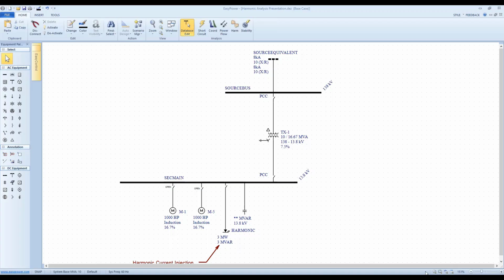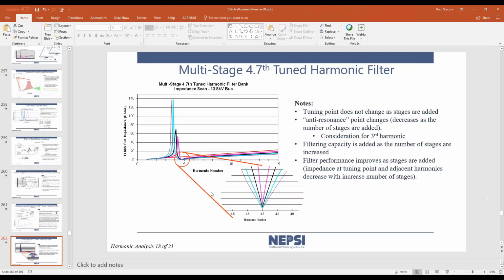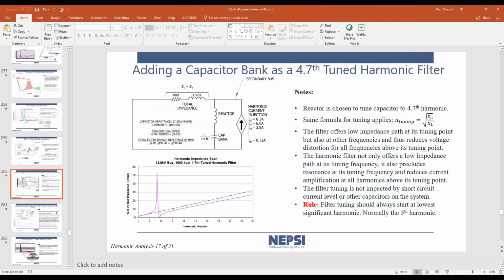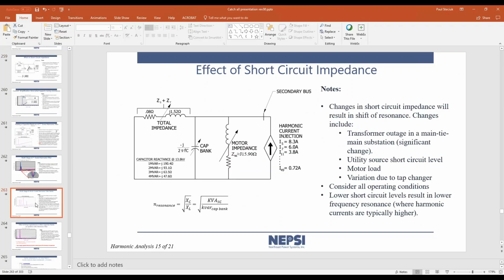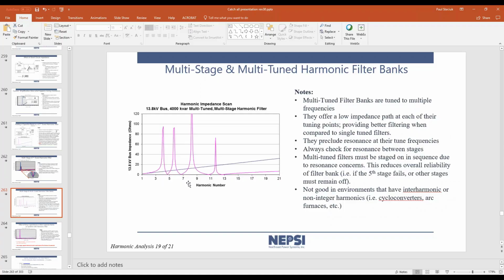And then the final question is, do you cover resonance or conditions that can be caused by filters? So first of all, harmonic filters. We go back to this, and what the question is saying is, hey, do you take care of this problem here, these resonance concerns, and here's a 5th, 7th, 11th, 13th harmonic filter, and you can see here this 5th filter causes a resonance beneath itself. This 7th filter causes a resonance between the 5th and the 7th.